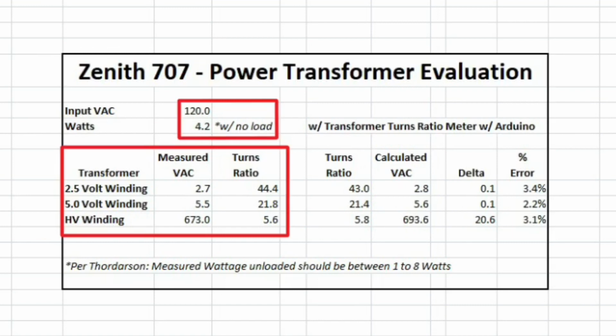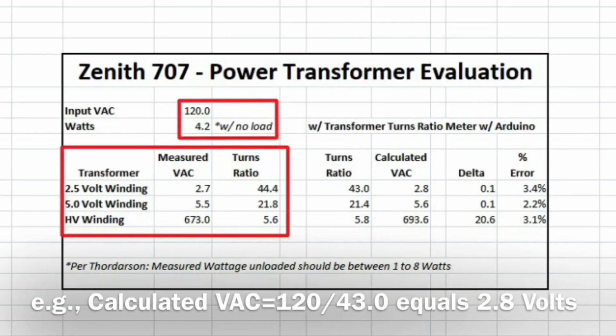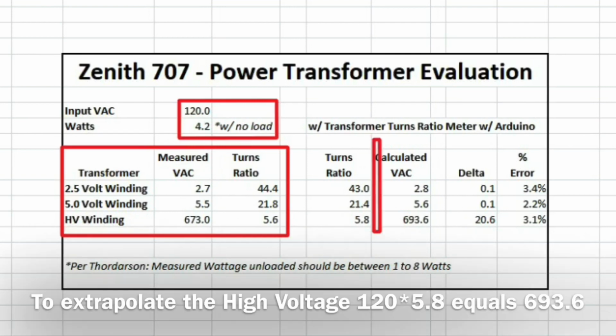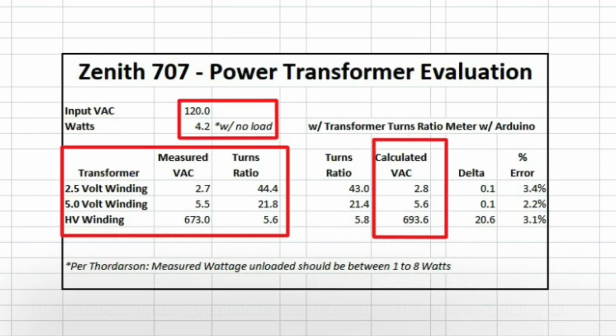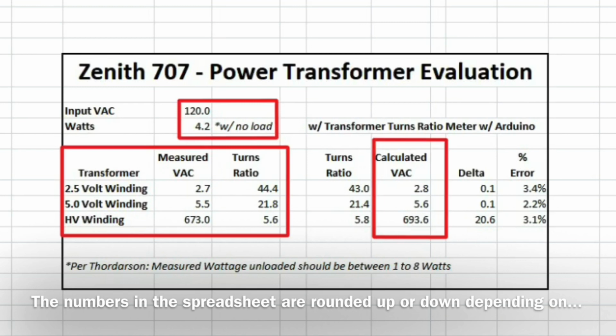And then we can go back into the numbers again using the 120 volts and calculate or extrapolate what the voltage would be. You can see the calculated voltages in this area, and they're relatively close, the biggest variance being on the high voltage winding. Everything falls around a 3% error rate, so still good enough to use this method.